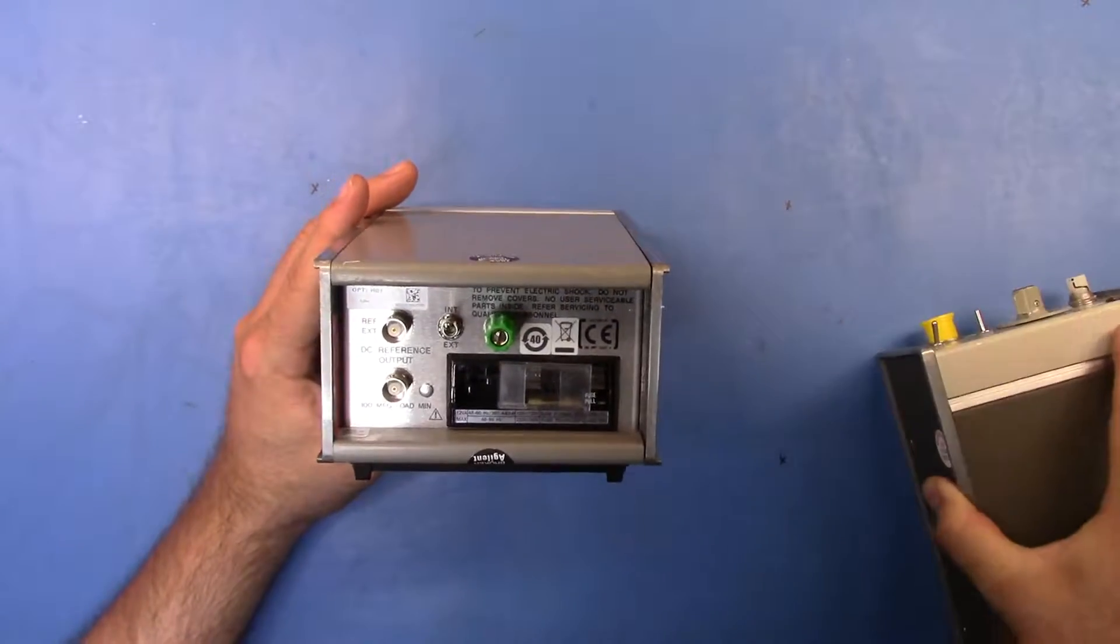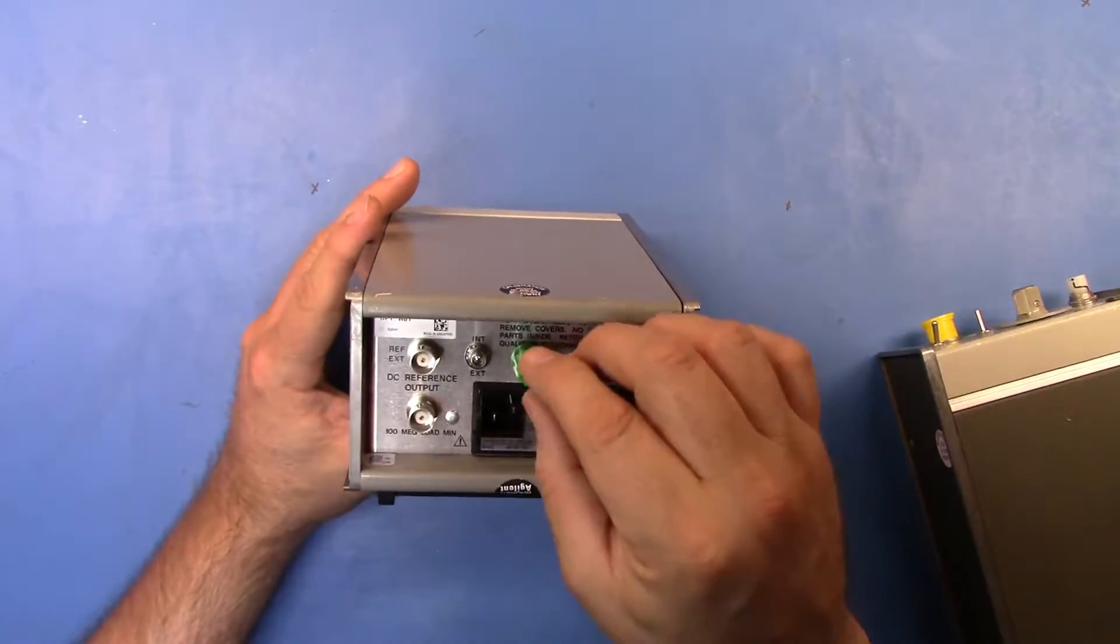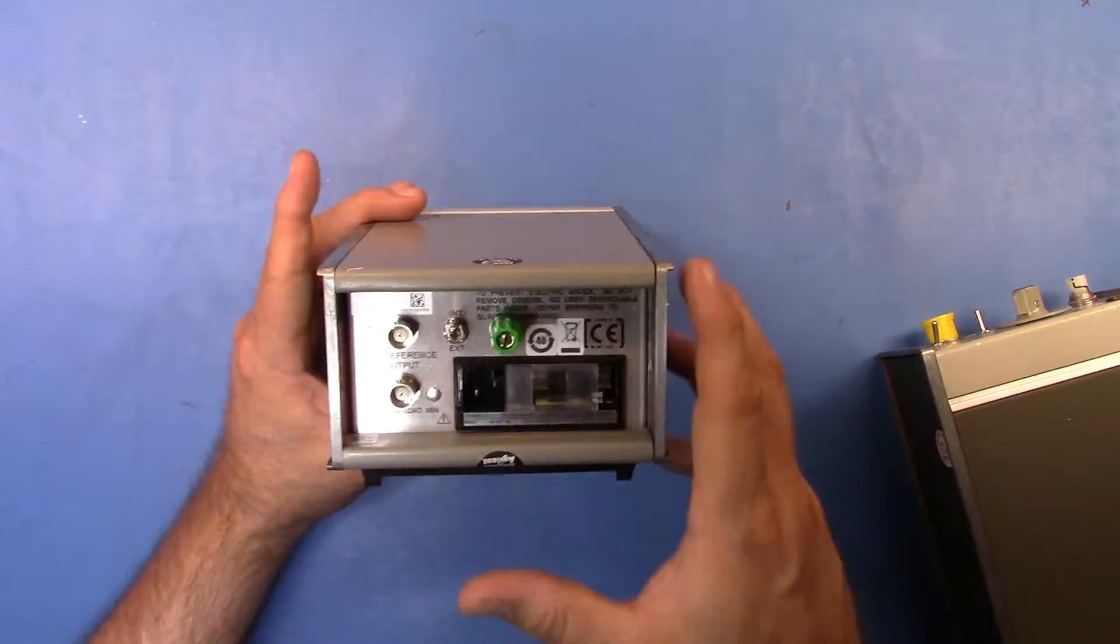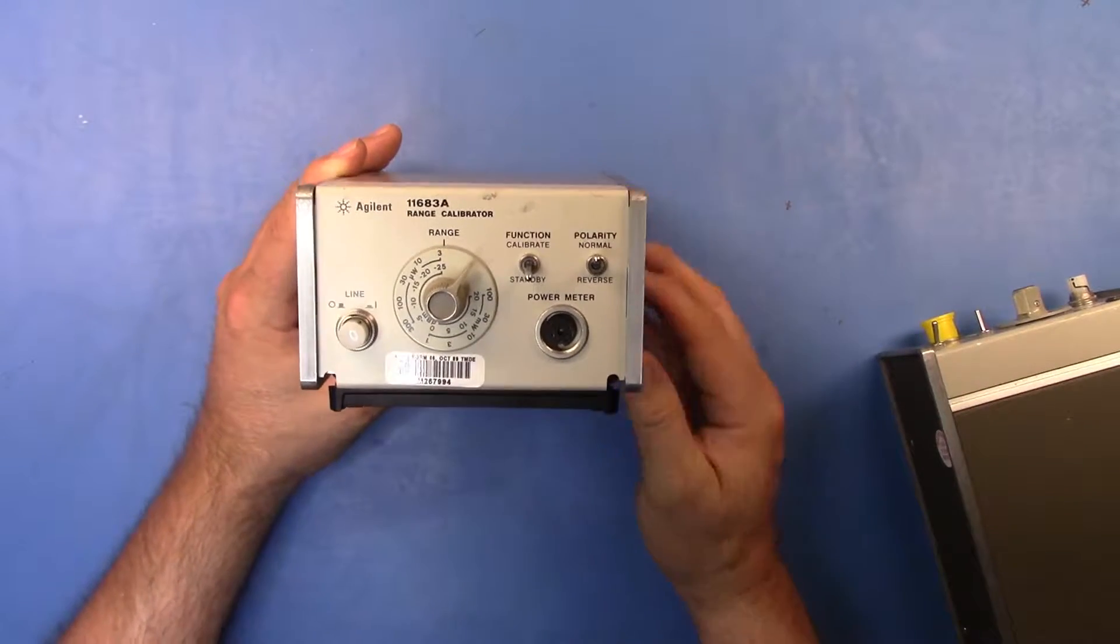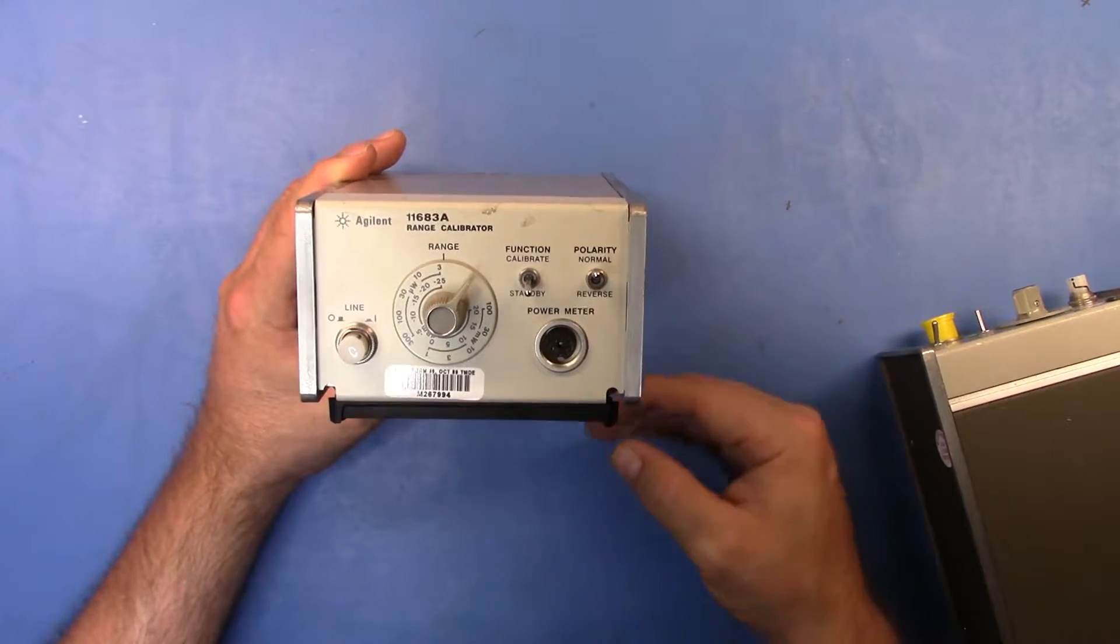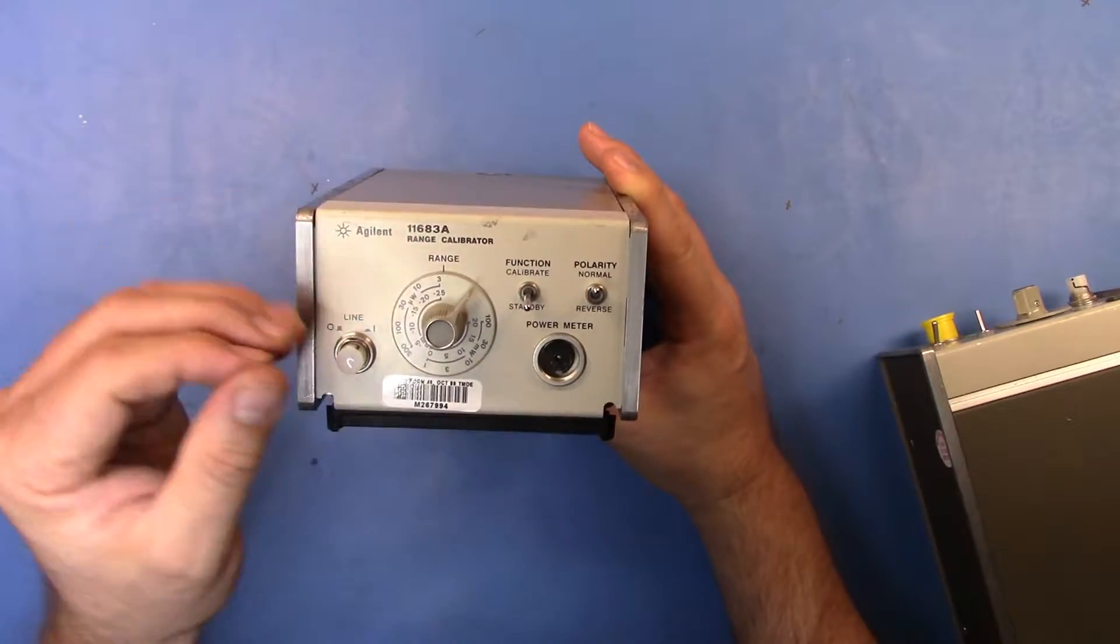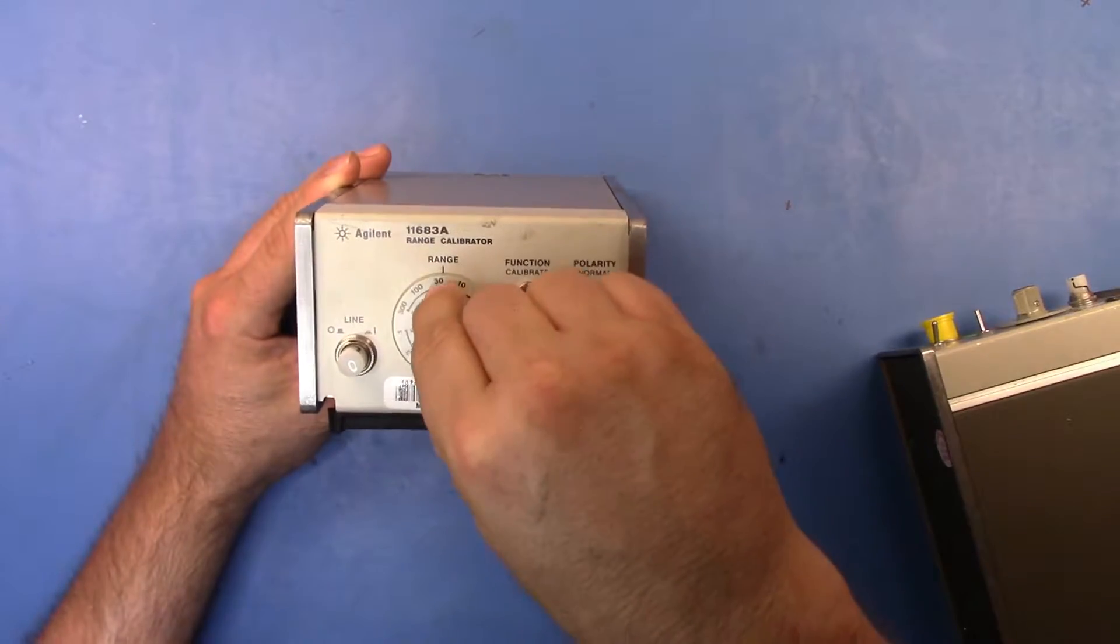What that option is, is it gives me the ability to put an external reference into this. How this thing works basically is that there is an accurate internal voltage reference that's set to 145 millivolts plus or minus 2 millivolts, and then it utilizes a voltage divider to create the individual voltages for each of the ranges that you see here on the front.